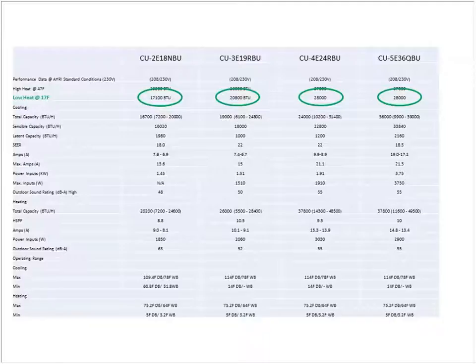Now, in Kotzebue, Alaska, their COP becomes a 1, based on their price of gas, at about 33 degrees. So literally, they're going to turn these off at 33 degrees and just go to gas heat. However, from 33 to 60 degrees, these things make them nothing but money, and they're thrilled about it. I, on the other hand, probably less so, because one of my challenges in Kotzebue is that the natives have never used ductless heat pumps and they're put in multi-zones. One caveat about a multi-zone system is that all the heads have to be in either heating mode or air conditioning. I can't put one head in air conditioning and one head in heating. So if you put one in a room that gets solar heat gain and they decide it's too hot and they don't want to hit air conditioning, it'll give you an error code. So it can be somewhat problematic.